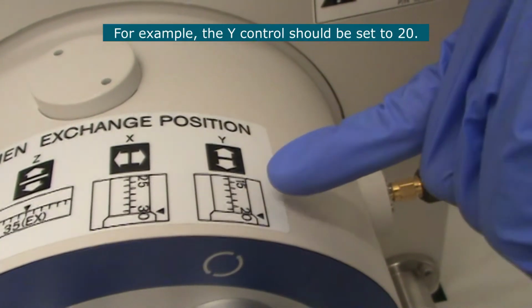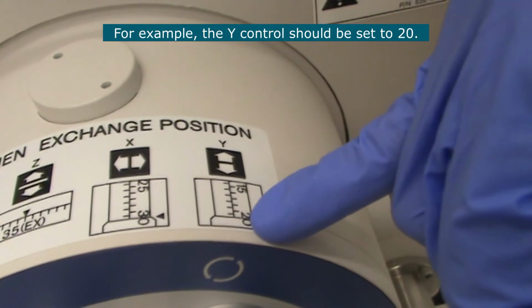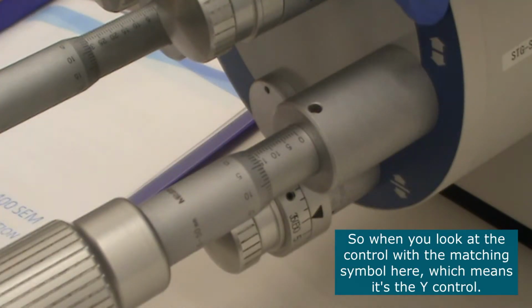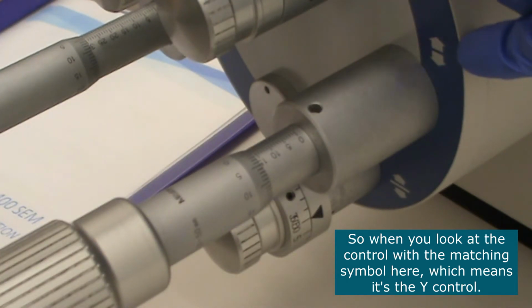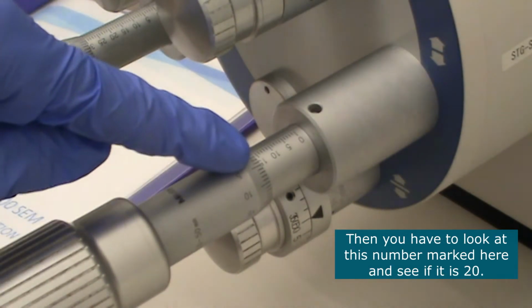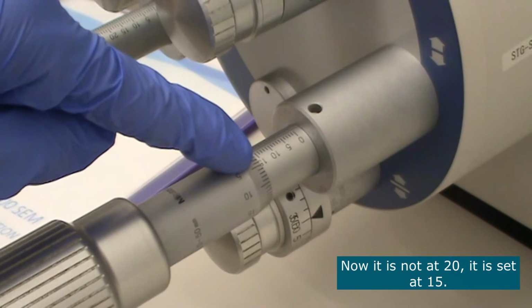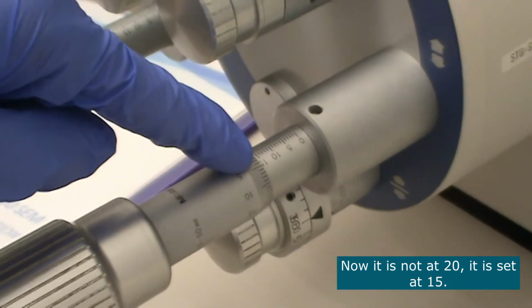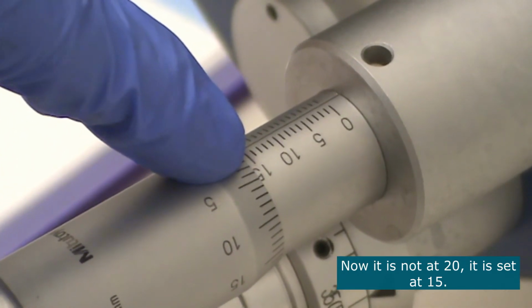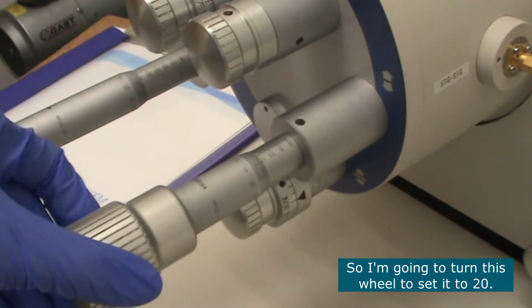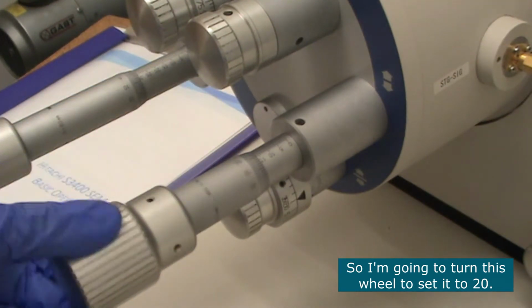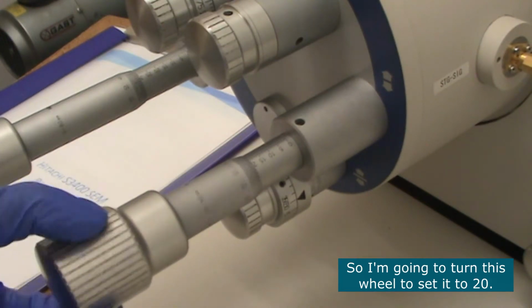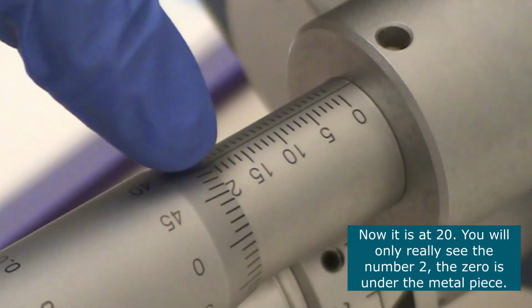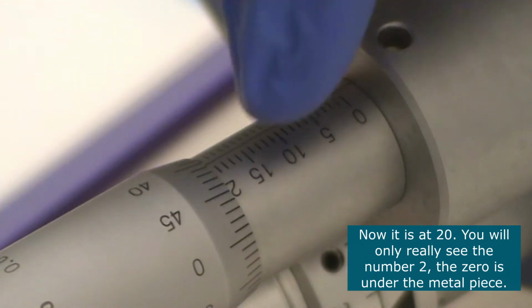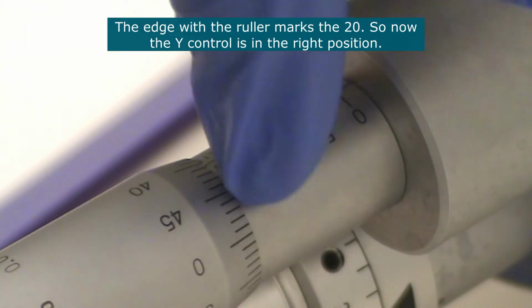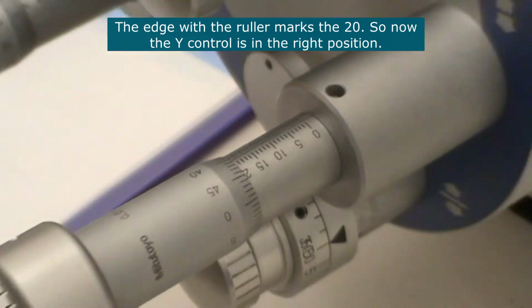For example, the Y control here should be set to 20. So if we look at the control with the matching symbol here, which means it's the Y, then you have to look at this number and see whether it's at 20. In this case, it's not at 20. It's set at 15. So I'm going to turn this wheel until it's at 20. Now it is at 20. You can see here the number 2 and you won't be able to see the 0, but this line here is marking the 20. So now the Y is in the right position.